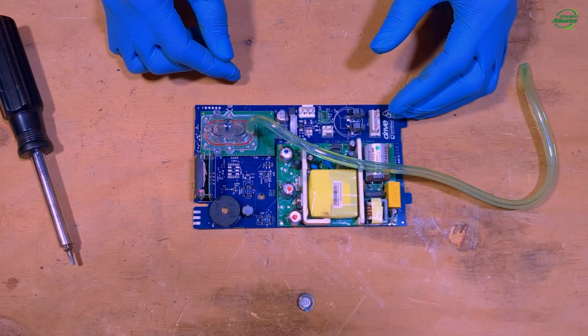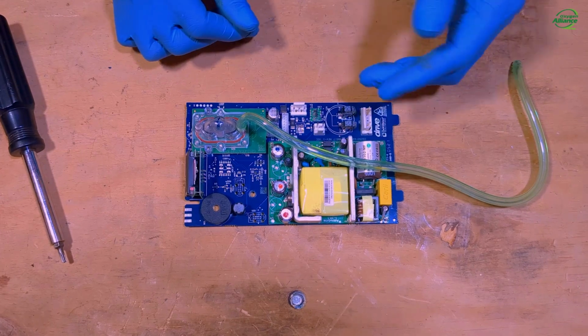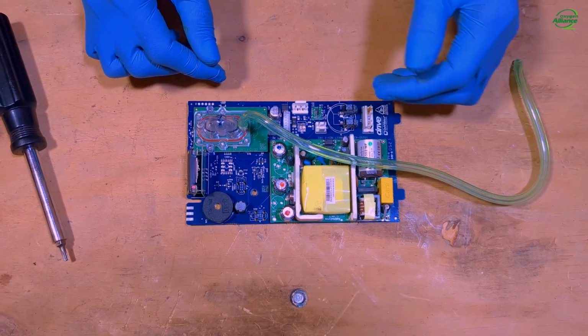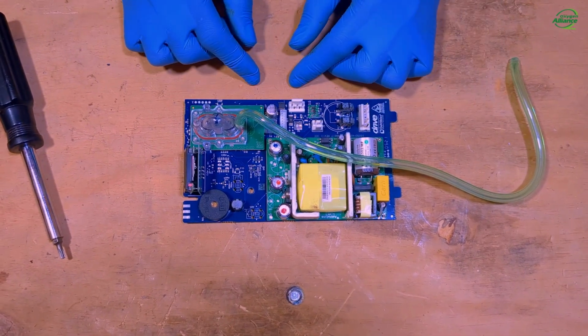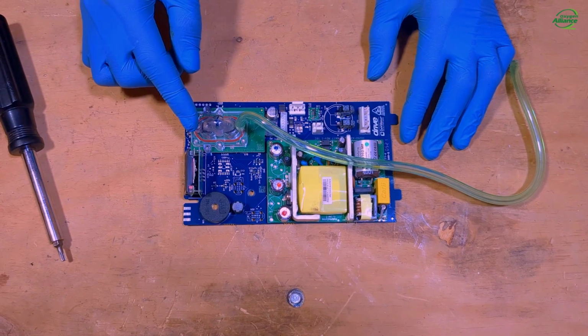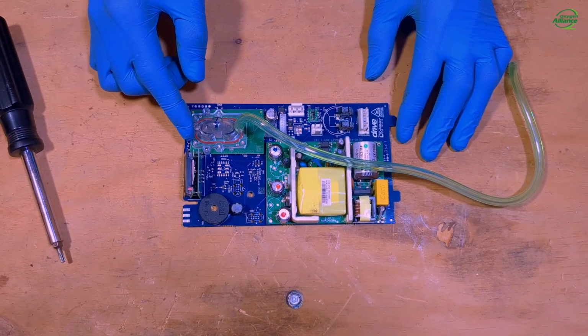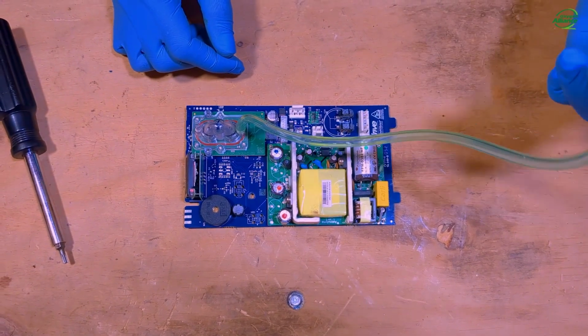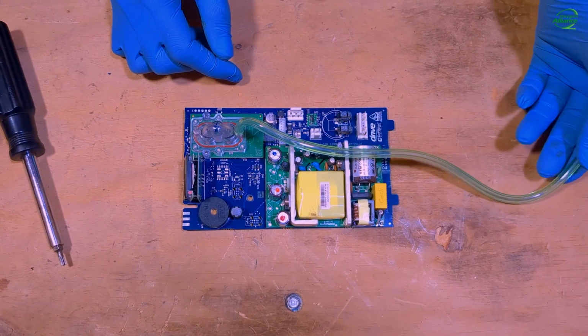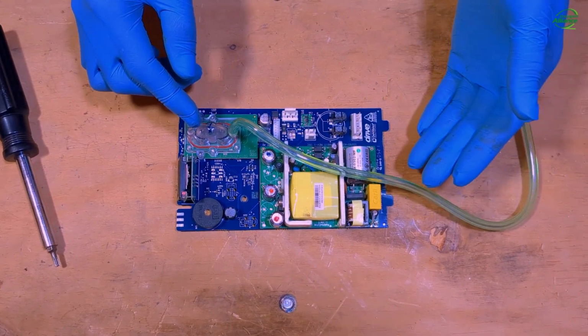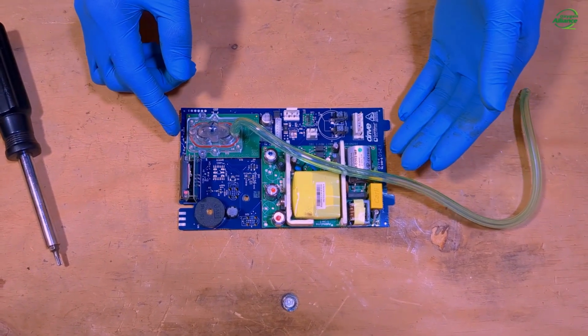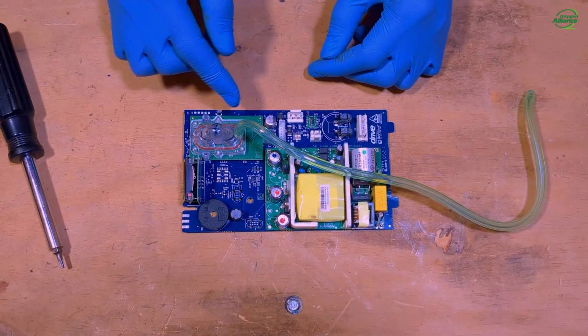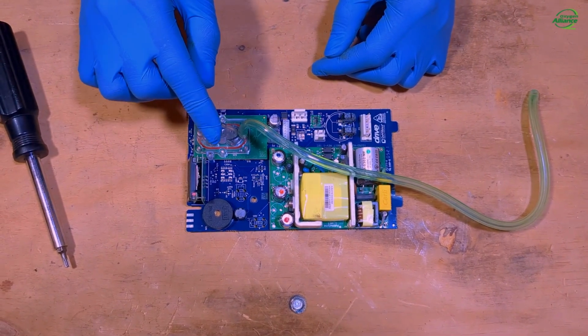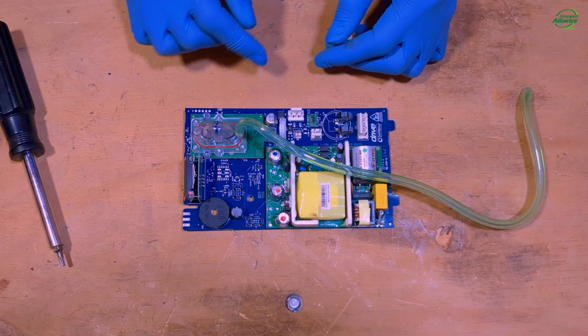So the main function of the OSD is that it measures and monitors the concentration of oxygen that is coming from the product tank. So this is where you connect the tube coming from the product tank, and this tube goes to the flow meter. So whenever the oxygen concentrator has a low purity alarm, it is because it has been detected by this sensor.